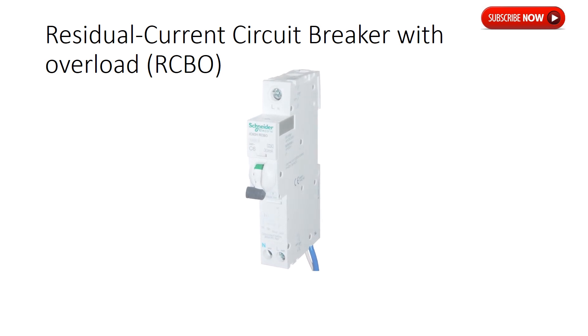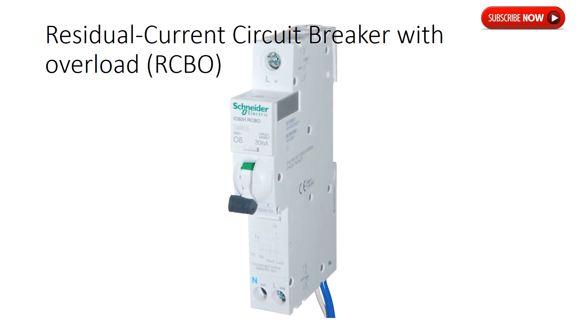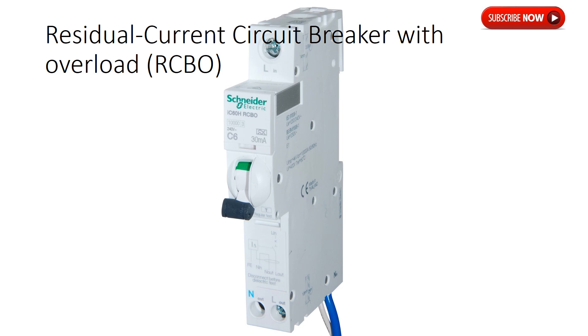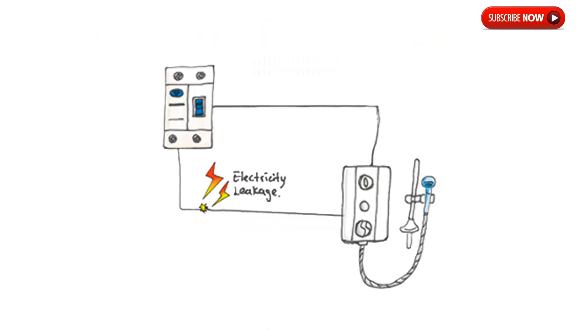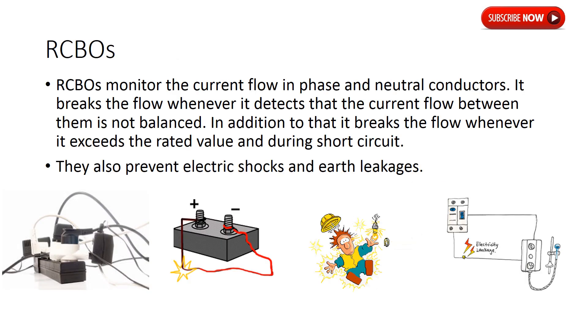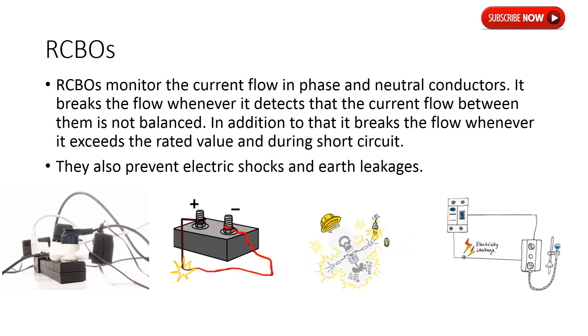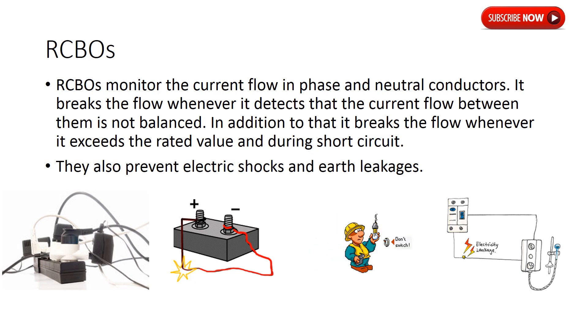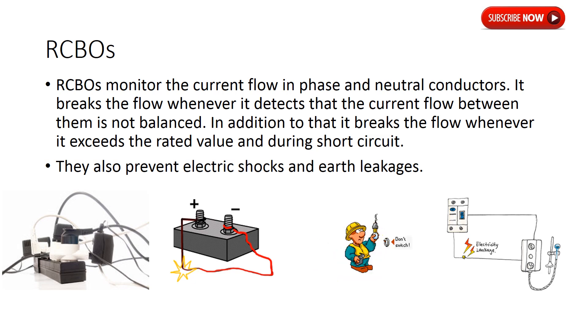RCBOs offer protection against overloads, short circuits, and electric shocks. It is a combination of MCBs and RCCBs. In addition to that, RCBOs can also protect from earth leakages and residual currents. RCBOs monitor the current flow in phase and neutral conductors. It breaks the flow whenever it detects that the current flow between them is not balanced, whenever it exceeds the rated value, and during short circuit. They also prevent electric shocks and earth leakages.